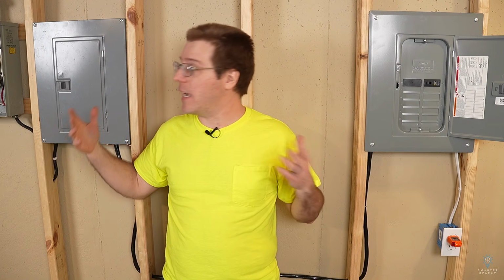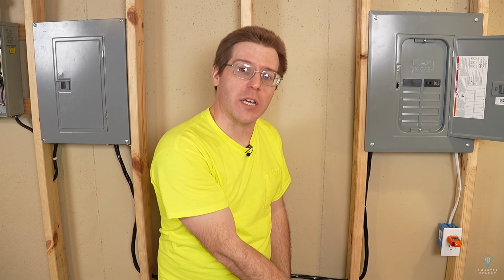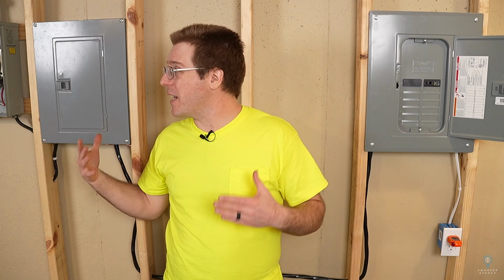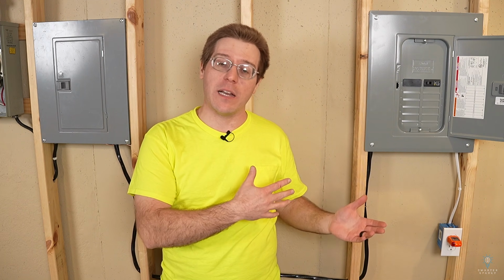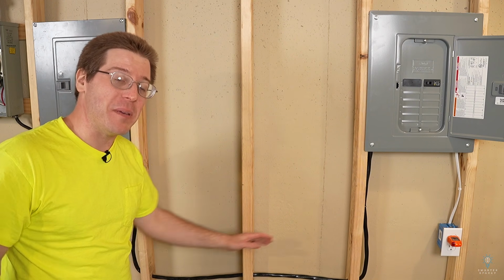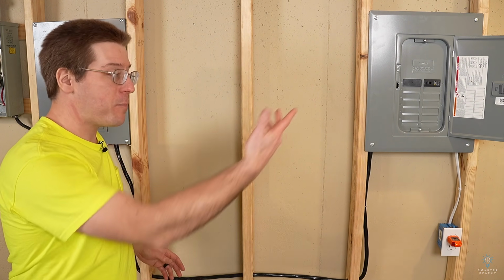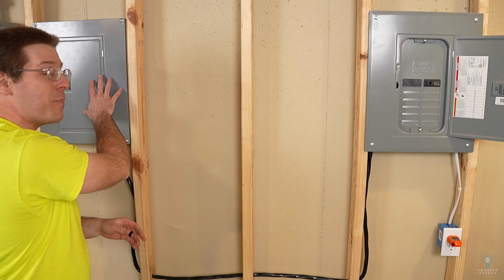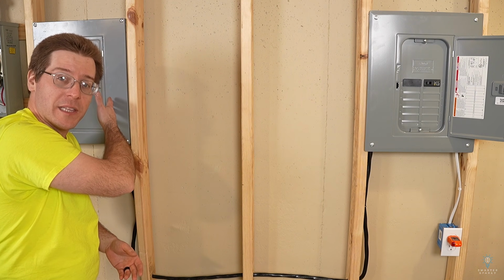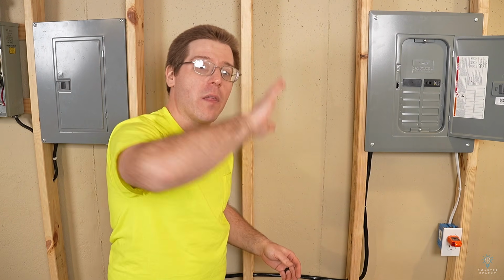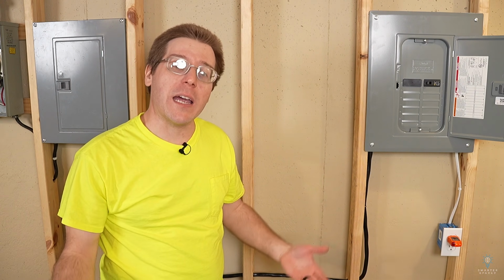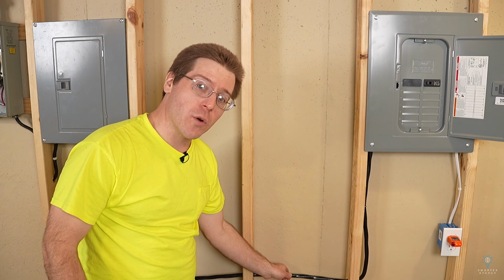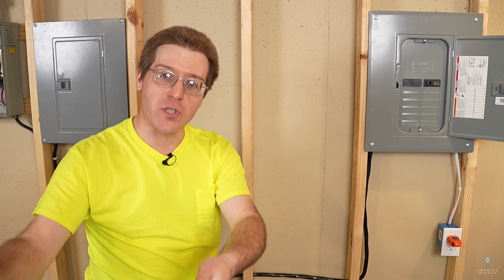We've just installed a sub panel and a branch circuit off of that sub panel to demonstrate kind of the difference between a main panel and a sub panel. Remember, this distance could be pretty much anything you need it to be. This panel could have been sitting right next to this panel, maybe because we ran out of room in this panel. Or this panel could be on the other side of a building because it's more economical to run one larger wire than it is multiple smaller ones.